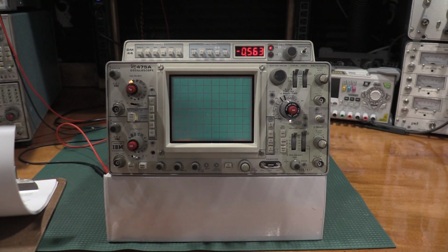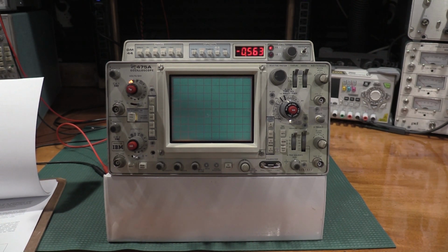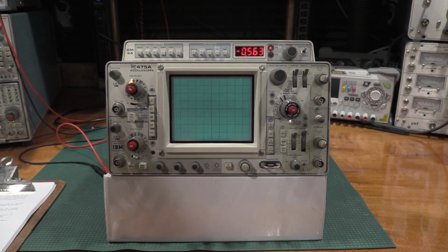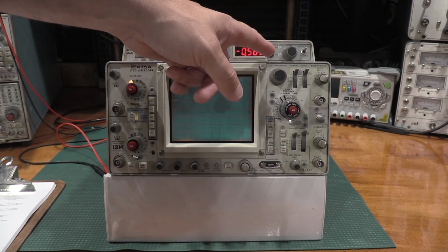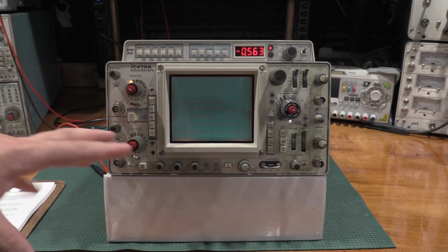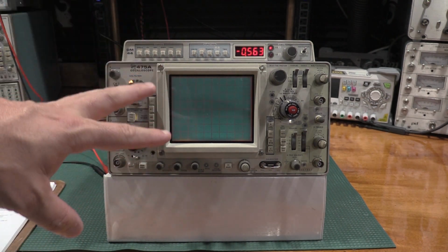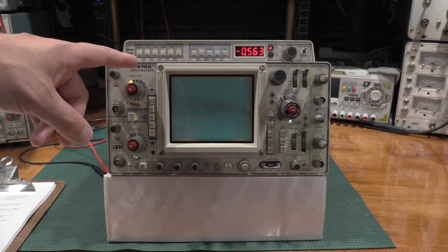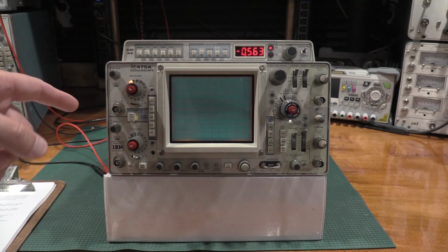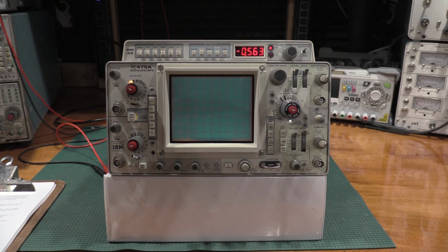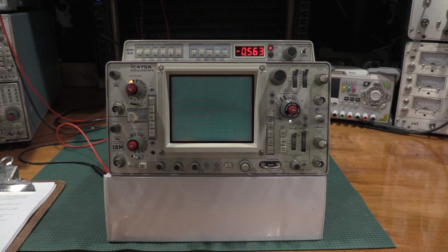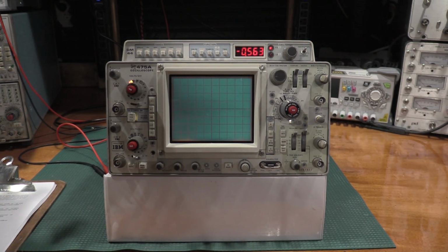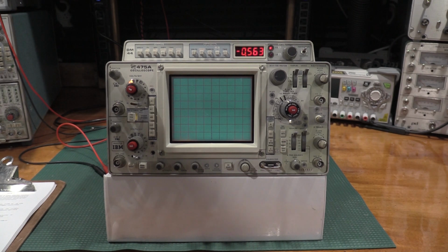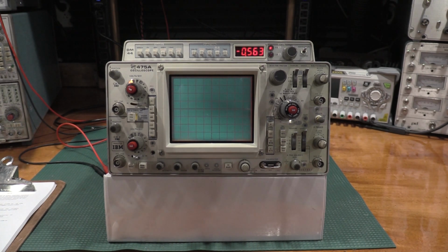This particular one, actually, I have to go up to the horizontal version, because with the integrating of the DMM into the scope, into the horizontal section, you actually need to do the horizontal alignment in the DM44 manual, not the scope manual. So for this particular unit, we'll do the display and Z-axis, the power supply, the vertical, and the triggering, and then when we do the horizontal, we'll flip over to the DM44, do its alignment as best I can. I don't have a temperature probe for it, but we should be able to align everything else.